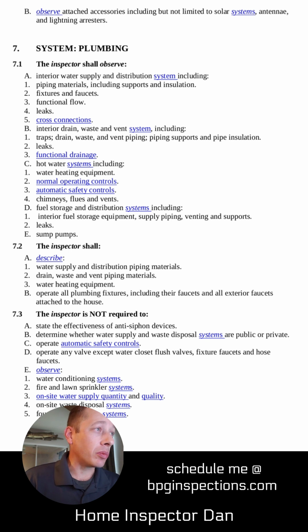C. The hot water system, including 1. Hot water equipment, 2. Normal operating controls, 3. Automatic safety controls, and 4. Chimneys, flues, and vents for the water heater. Section D, the fuel storage and distribution systems, including the interior fuel storage equipment, supply piping, venting, and supports, and also if any leaks are occurring. We're also required to check the sump pumps.